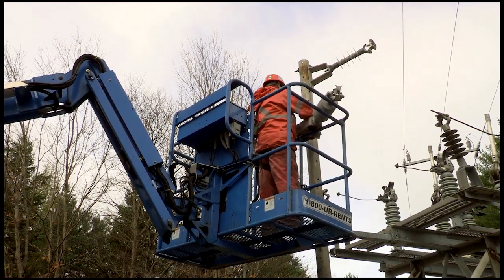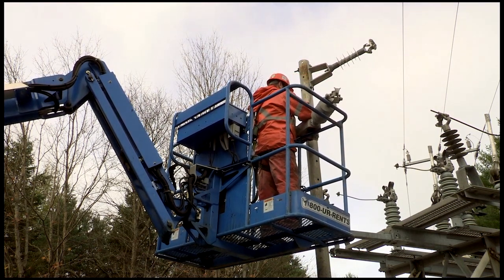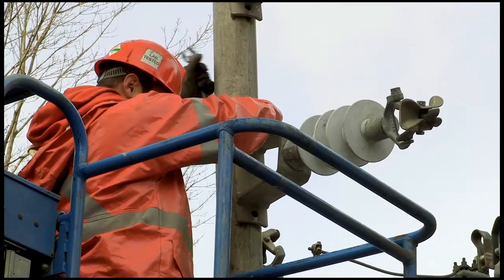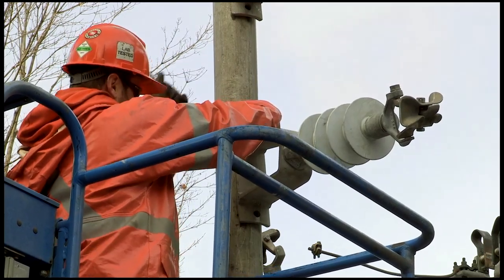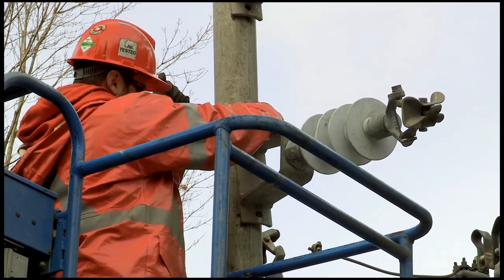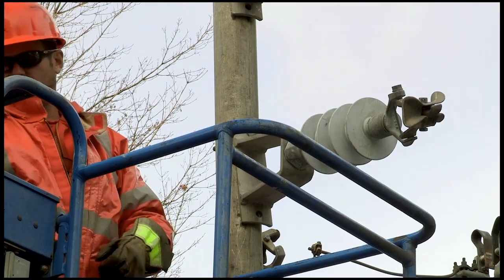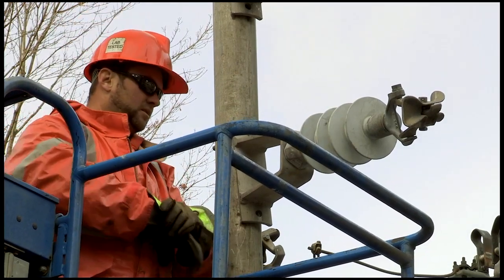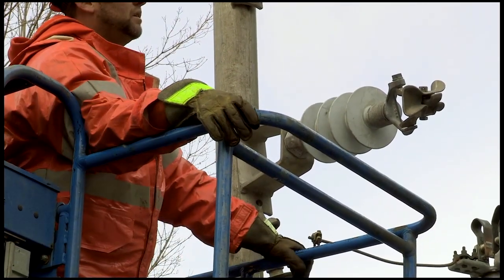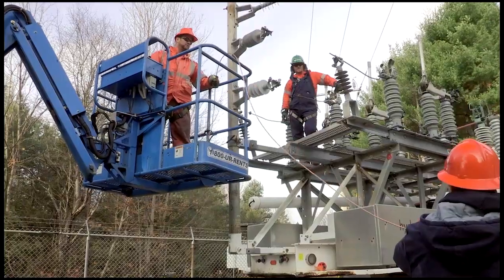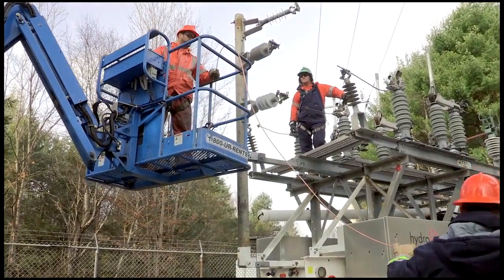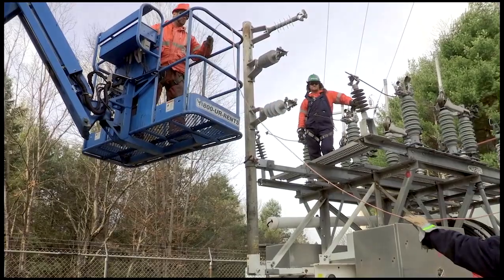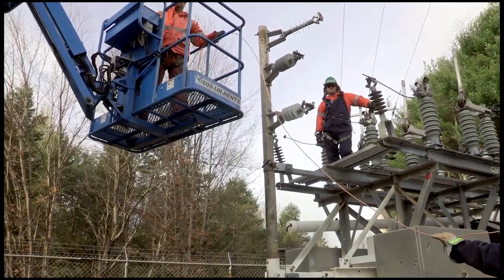Install the 3 mast insulators, starting with the blue phase, then white, and finally red. This can be a trial and error process because once all 3 leads are installed, you might not have the proper phase-to-phase clearance. Depending on the placement of the mobile, you might have to use more than 3 insulators to bring the leads around the mast.